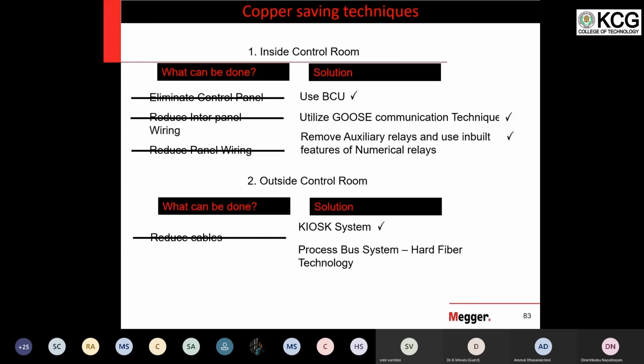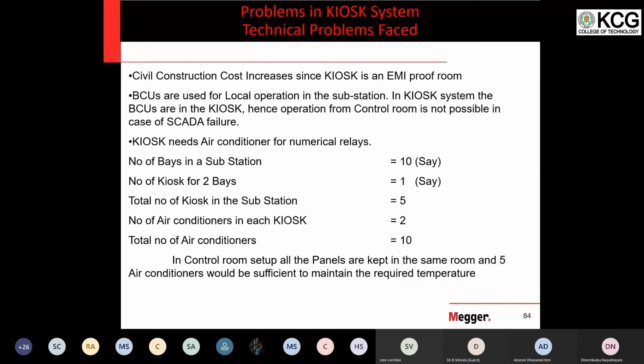Now we are going to discuss a technology. This technology is going to change this. Now, before going to that, first we have to understand why this is not called a smart system. The reason is there are some disadvantages in the kiosk system. So now let us see what the disadvantages in a kiosk system are. The second line that you see here, this is the biggest disadvantage. BCUs are used for local operation in a substation. In the kiosk system, the BCUs are in the kiosk. Hence, operating from the control room is not possible in case of SCADA failure.